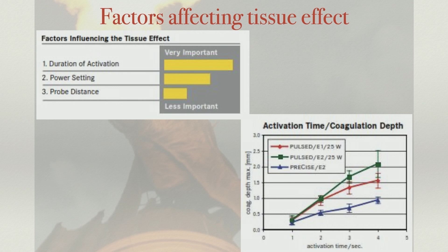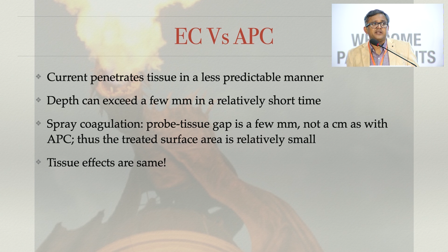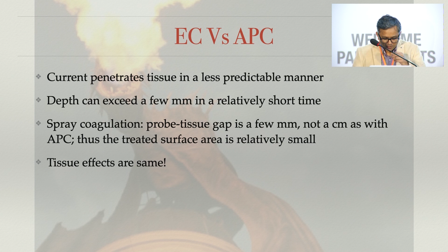Now let's compare APC with electrocautery. In electrocautery the current penetrates tissue in a much less predictable fashion when compared to APC. So it is quite erratic, therefore APC scores over electrocautery. The depth can exceed a few millimeters in a relatively short period of time, and spray coagulation is possible. Tissue effects though are the same.